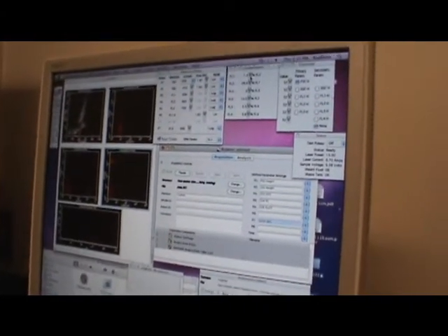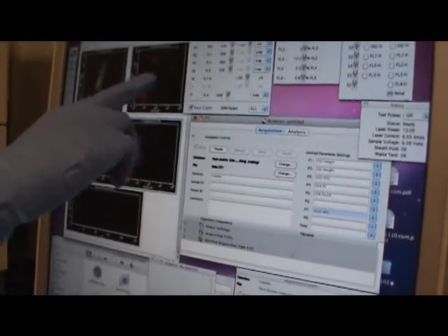There we go. See? I just want to show you. Pause, restart. So now my PE, because I gave you the calibration file, everything looked very perfect. But I'm changing it to show you when you need compensation.